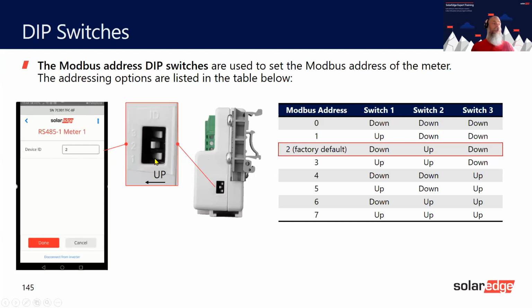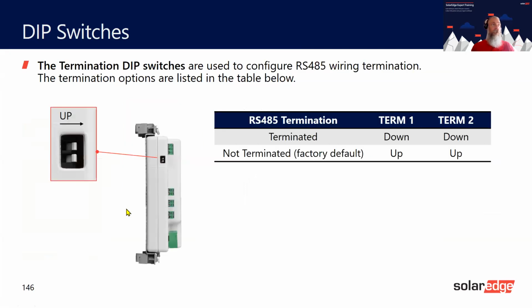Now, bear in mind, you can also have it as 1 or you can have it as 3, whatever you wish, but you must have the correct number in there. These are the termination switches. Again, they must be terminated, not terminated. So factory default are up and you must put them down. Okay, so these are up and factory default is up. So as they are basically when they come out of the factory, you shouldn't need to do anything.